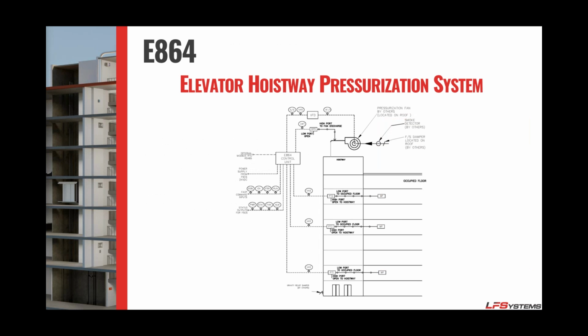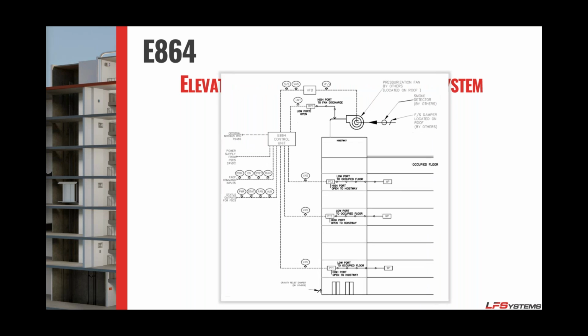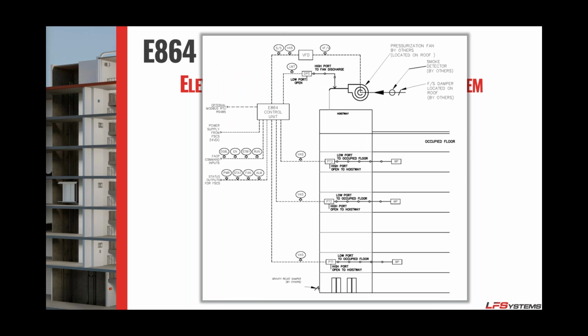This is a system diagram showing the different components. Again, this is just a sample, but it could be slightly modified. Zooming in a little bit, we have our E864 in the middle. We get our inputs from the control panel. All of our statuses as required by code go back to that panel. We get our power from the FSCS. We do have an optional output for Modbus, so if you want to tie this into your BMS for your weekly testing system to report, that would be a great option.